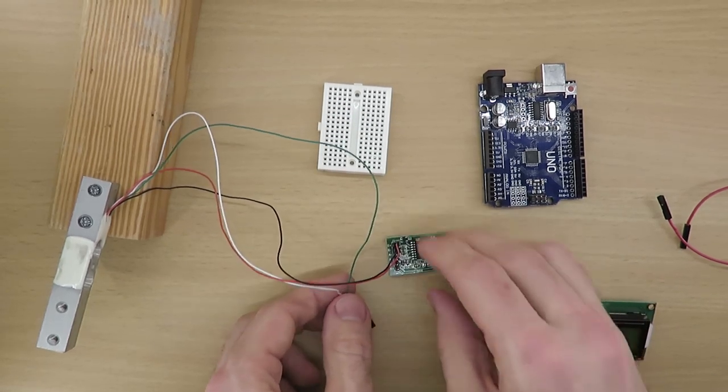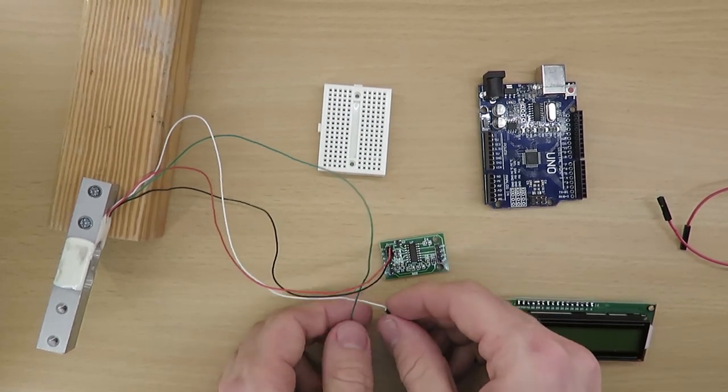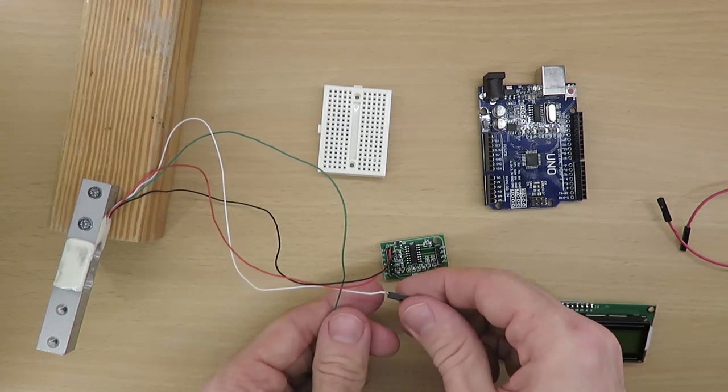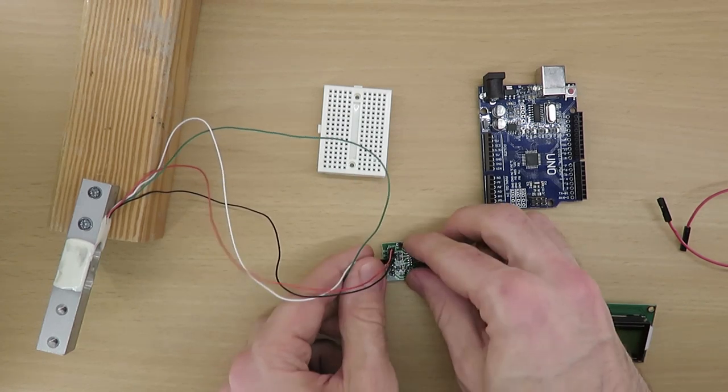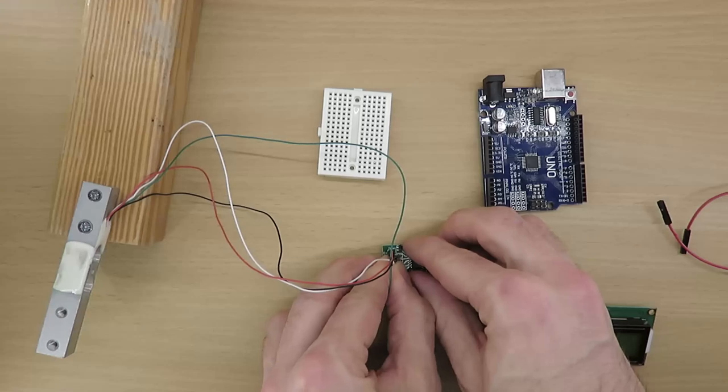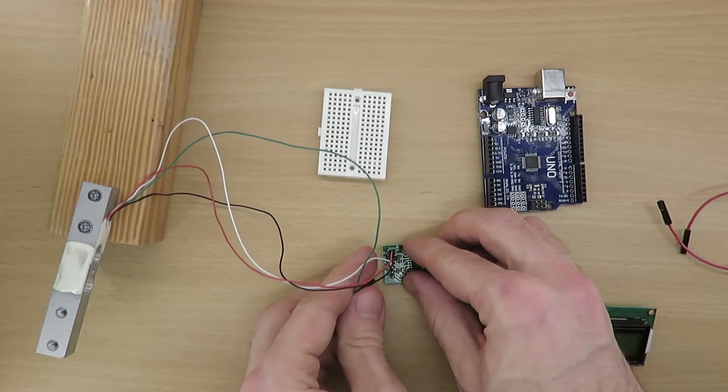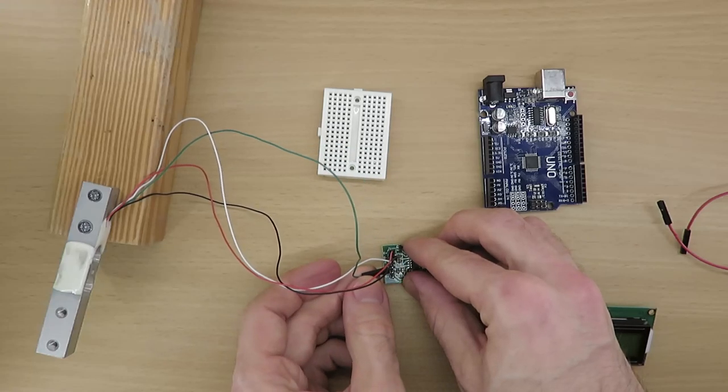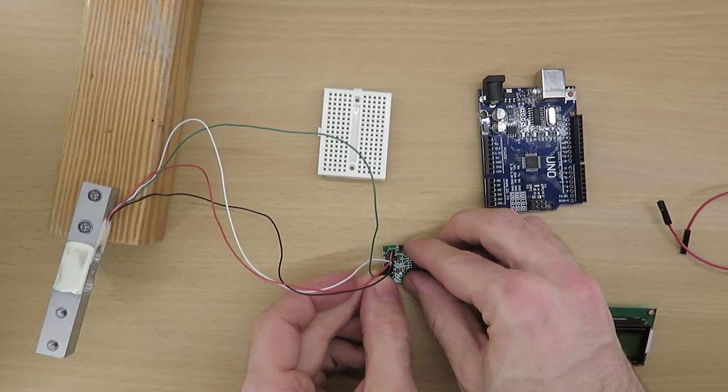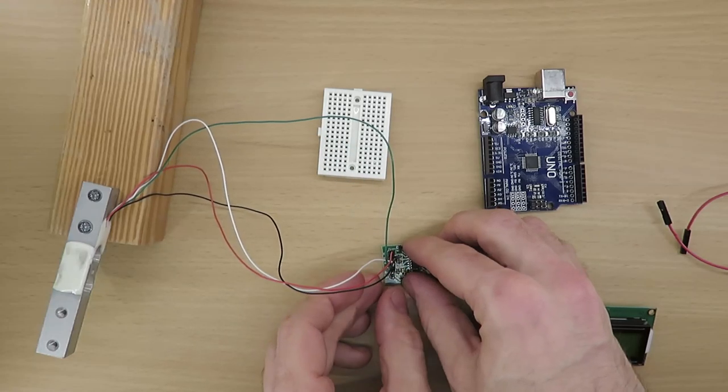Black has to be connected to the E minus pin. By the way, E stands for excitation. Then the white wire has to be connected to the A minus pin. And the remaining wire, the green one, must be connected to A plus.